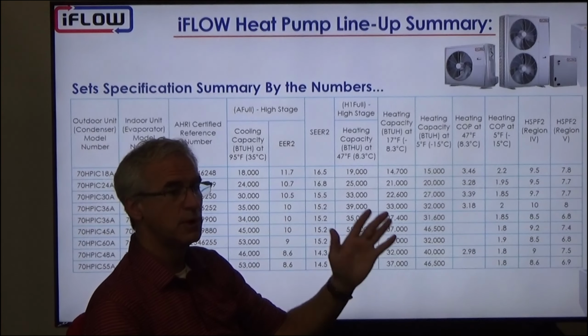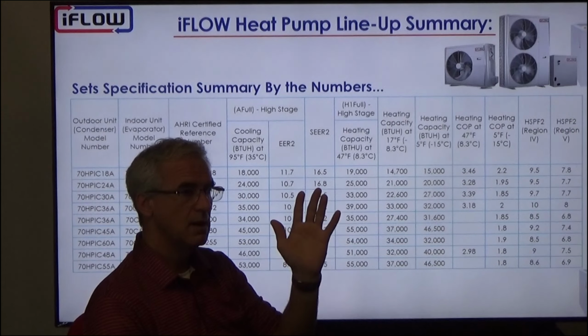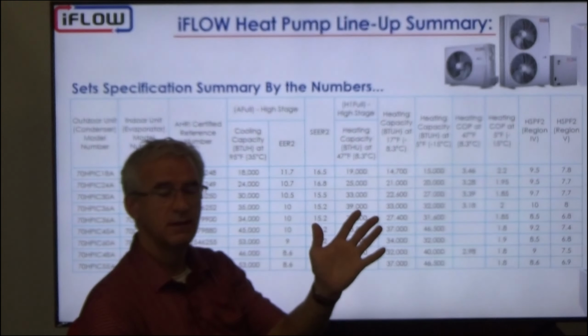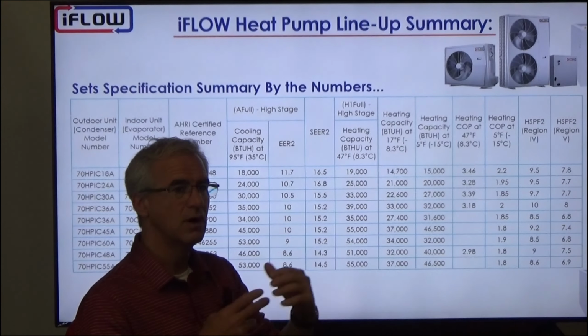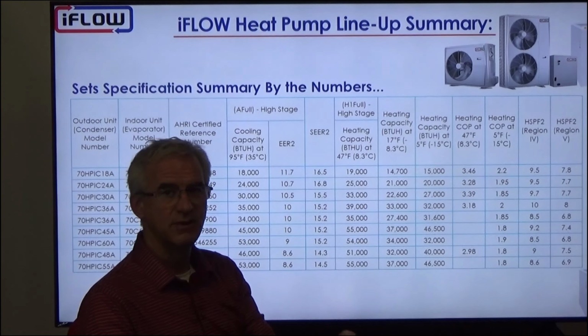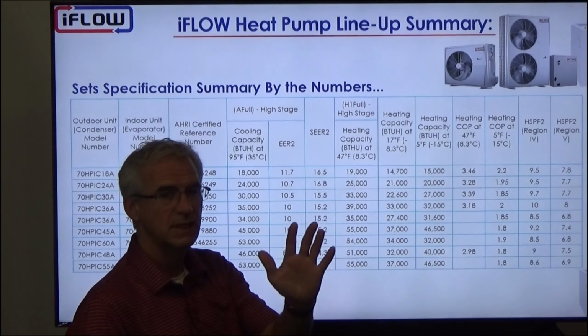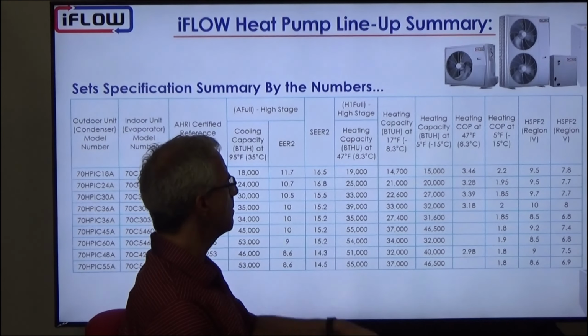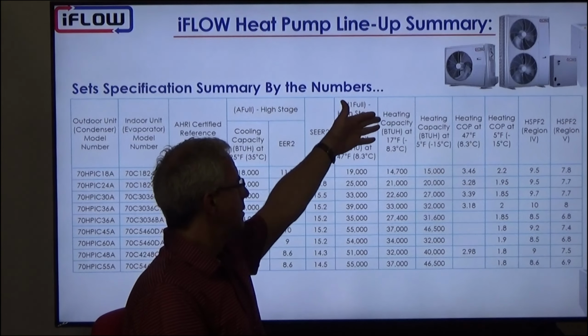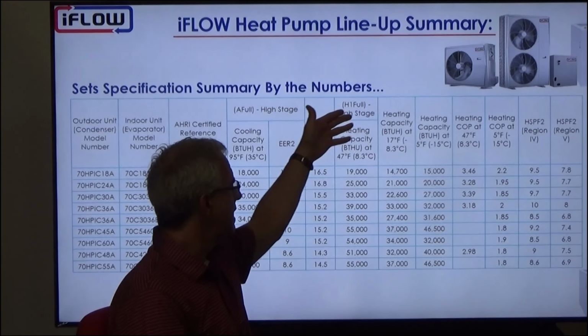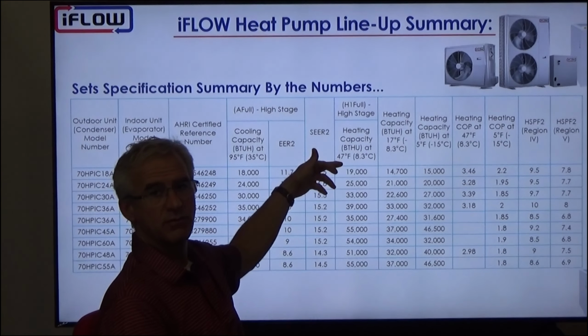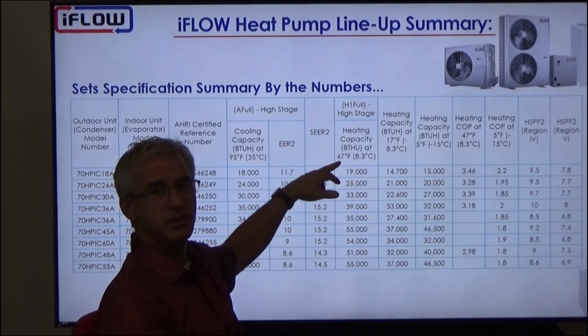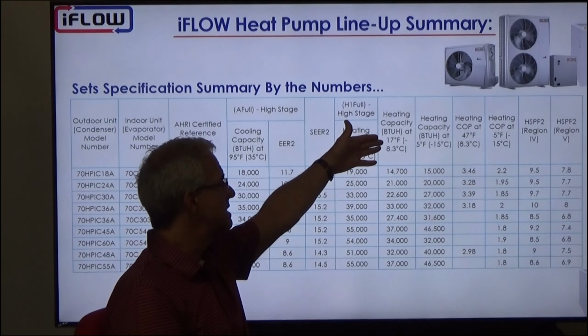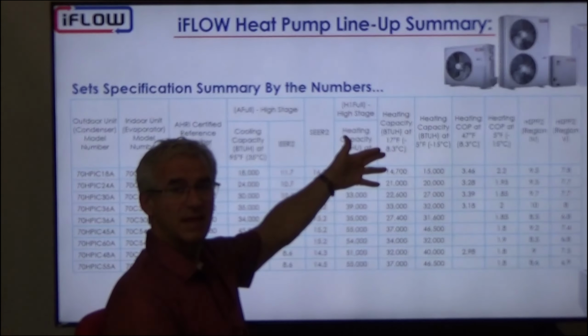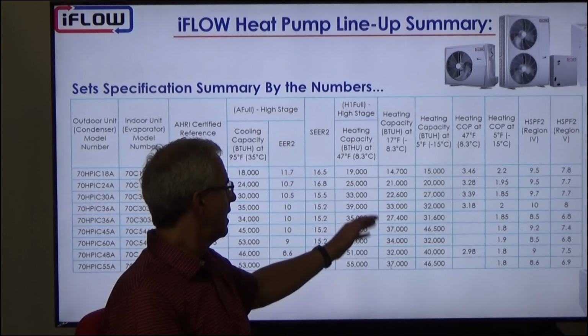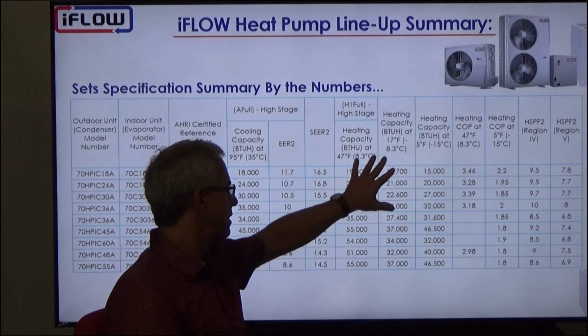So as the heat pump gets colder outside, the heat pump will have a harder time pulling the heat out of the air. So the actual performance drops a little bit, but we'll go through that as well. We'll look at how much, but we have the heating capacity at an outdoor temperature of 47 Fahrenheit or 8.3 Celsius, and then we have it at 17 Fahrenheit or minus 8.3 Celsius. So you see the BTU capacity.